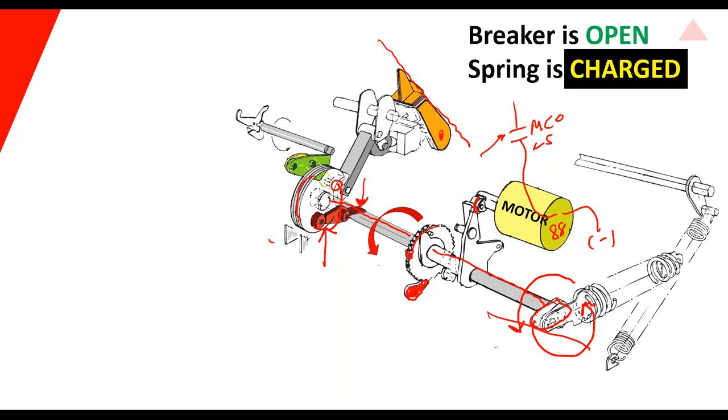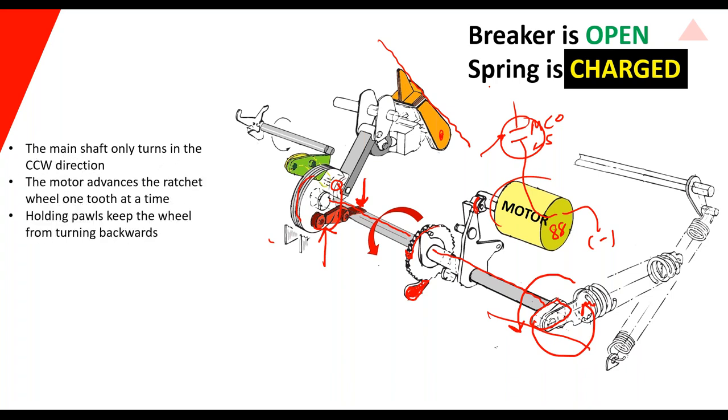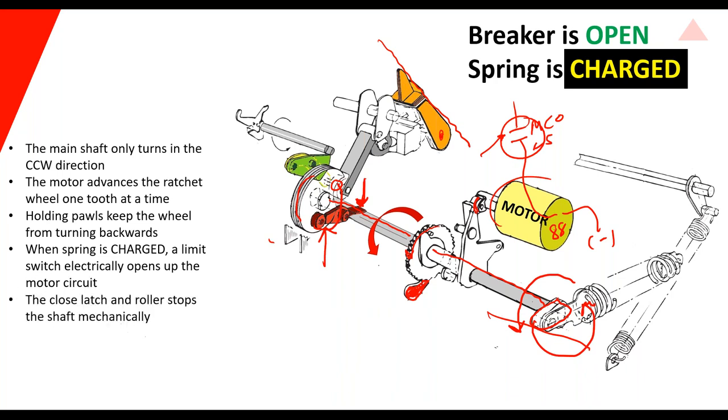Electrically or with a push button, you move the close latch and let the breaker go closed. If it's slow or sluggish, it's probably a lubrication problem — too much of the wrong stuff or not enough of the good stuff. If it never charges the spring at all, it's probably in the motor or in the motor circuit, maybe the limit switch. So the shaft turns counterclockwise, the motor advances the ratchet wheel one tooth at a time, holding pawls keep the wheel from turning backwards. When the spring is charged, the limit switch electrically opens the motor circuit, and the close latch and roller stops the shaft mechanically.